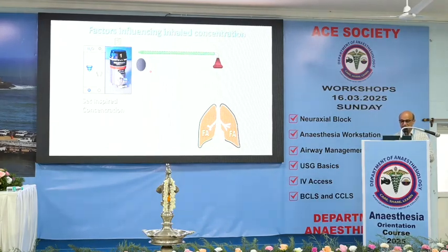The peculiarity about this anesthesia breathing circuit is that some of the molecules may also get adhered to the surface. So there may be rubber gas solubility, or even PVC or plastic gas solubility, and they may not be delivered in the amount which you have set here, like insulin. Some of it gets adhered to the drip set. Similarly, some vapors which you have set here are stuck here and they are not delivered to the alveoli.